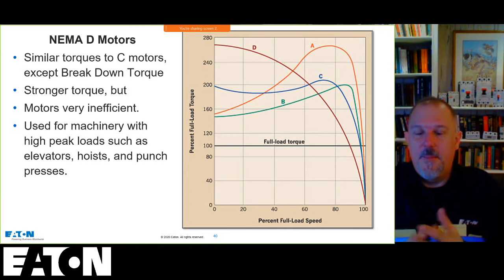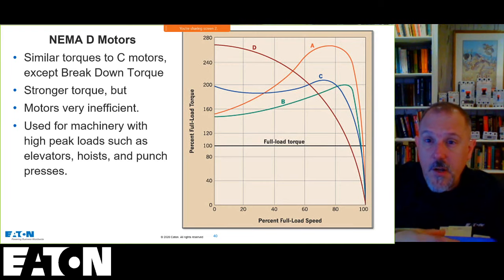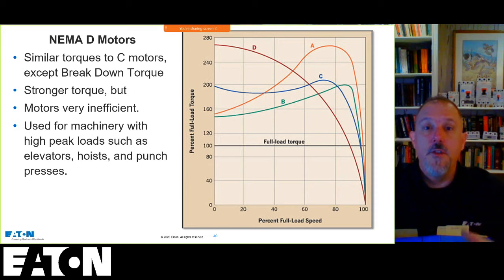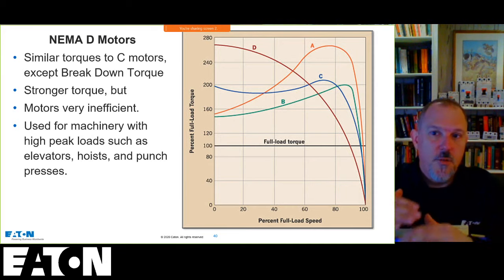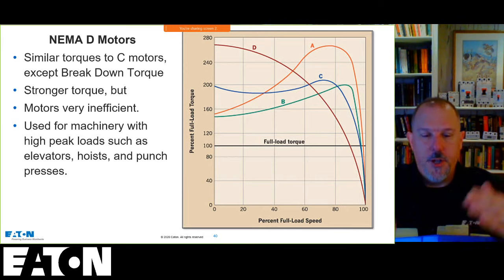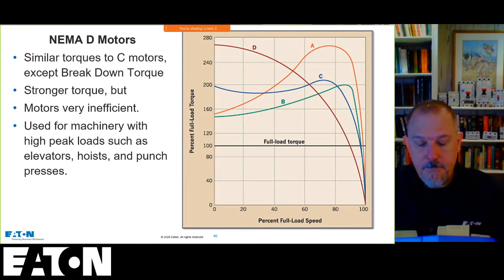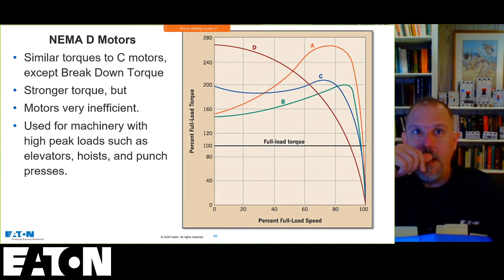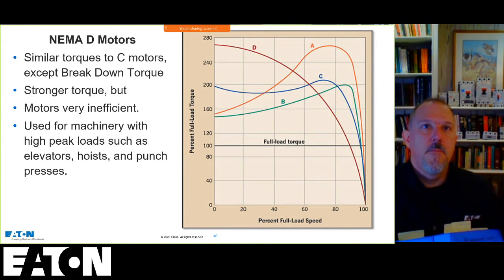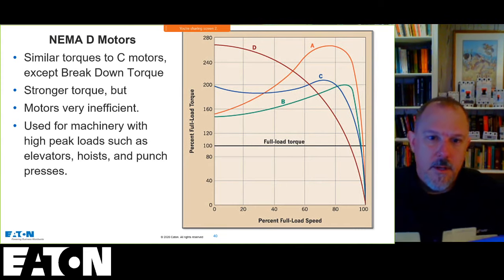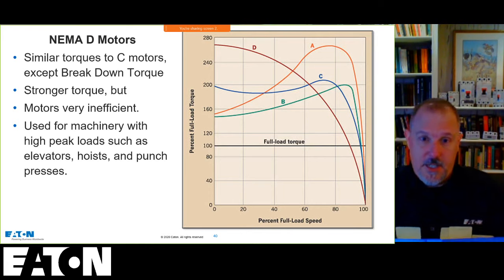I just saw a note up here about D motors. The reason is because you're either going to be changing frequency or changing voltage, changing one of those parameters to vary the speed of that motor, which will change your full load amps and your currents. And it could be that you are going to have a value that's outside of that table. So good point. Thank you, Mr. Fahey. Why we got you, buddy. It'll be a little less in your next paycheck for that answer. All right.